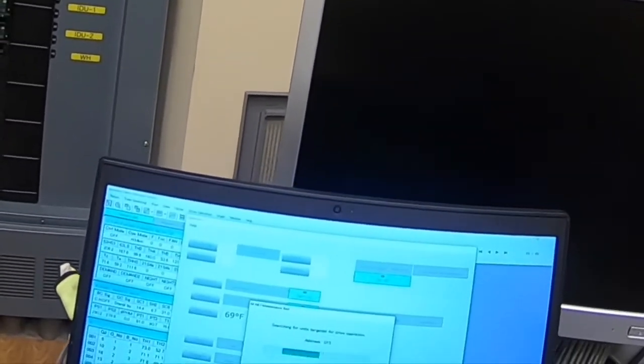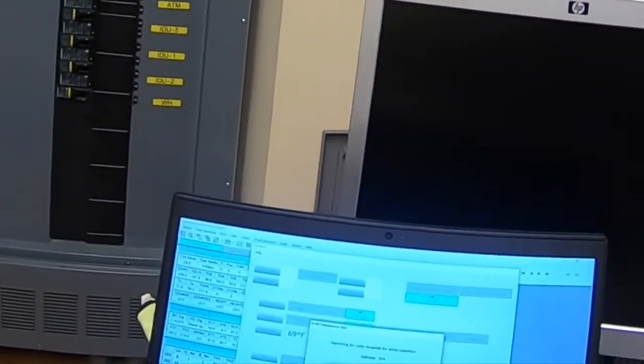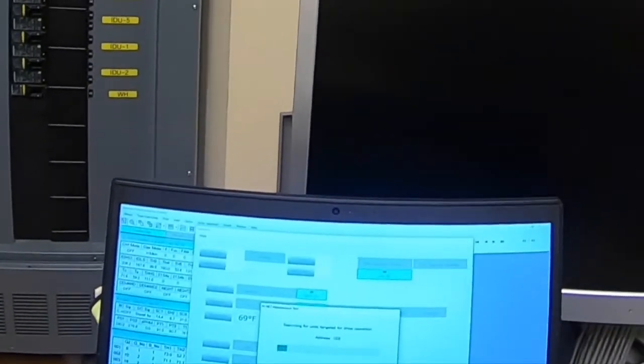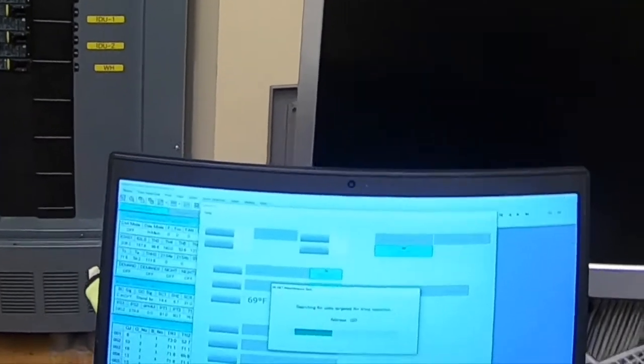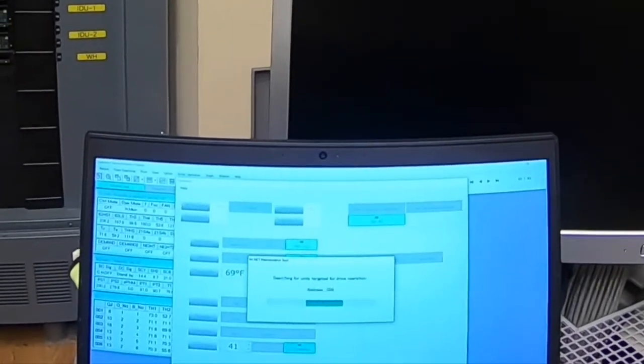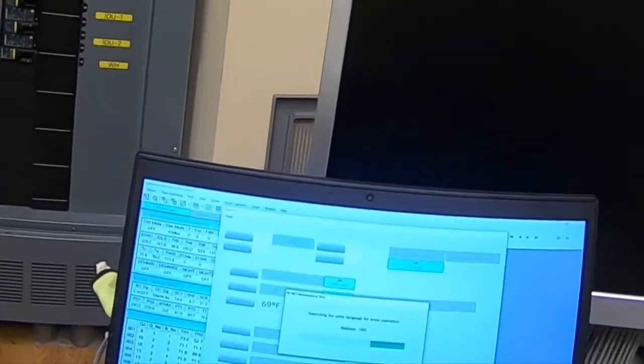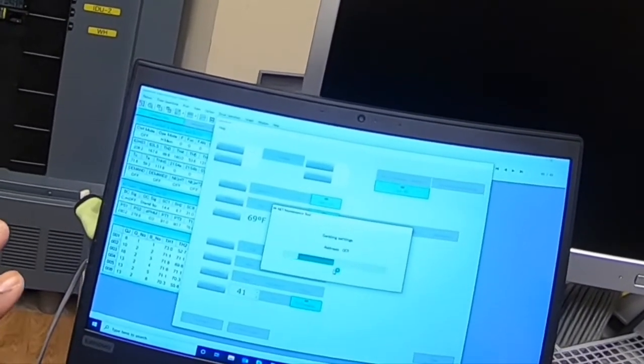Now it's going to transmit all that data I just set to the controller, which tells the outdoor unit what to do, because that's where the actual control board is. So I'm sending a message to the outdoor unit telling it I want to put the whole building in test mode, and it's confirming yes, that's what it's doing now.